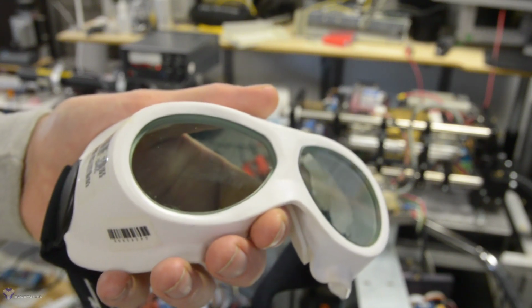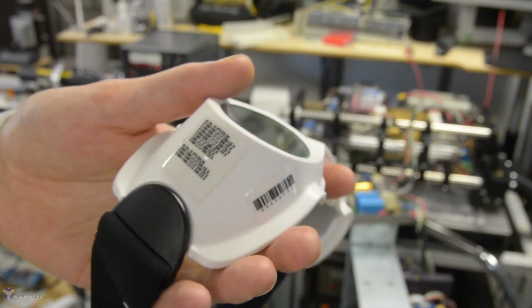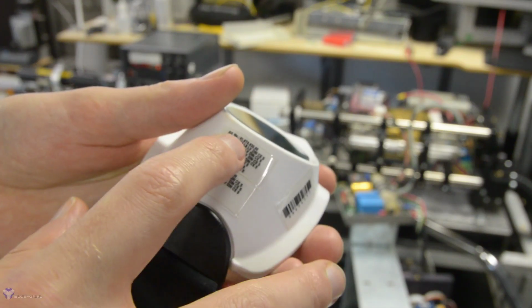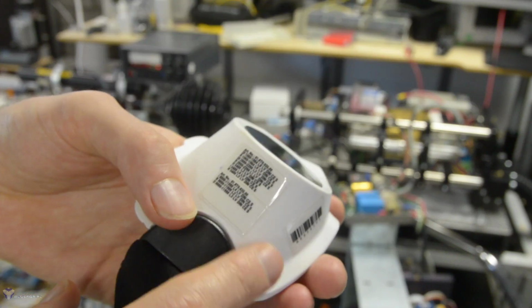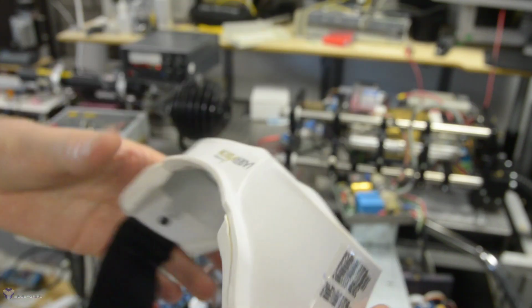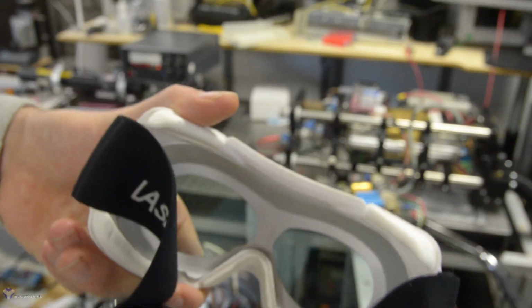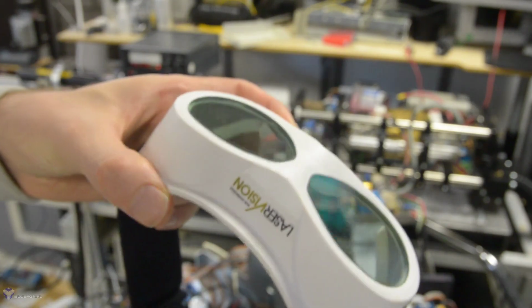Now, if you look in the laser safety standard, then the rating of the goggles should be at least L6. So you're looking for the D for continuous wave lasers like this. At 1064 nanometers, the L6 protection protects you up to 10 watts per square millimeter. And for L5 it's only 1 watt per square millimeter, which is definitely less than this laser can output. Well, these goggles can do L8, because these are really quite strong, thick filters, steel insert, so these will be absolutely fine.